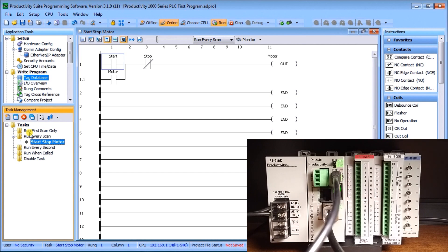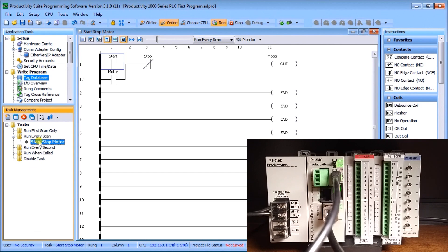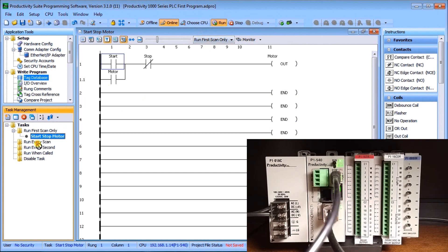Under Task Management there are several run options: Run First Scan Only — ideal for resetting values during initial PLC boot-up; Run Every Second — good for math operations that don't need to run every scan; Run When Called; and Disabled Task, where you place programs under development before moving them into the active program. To change the task type, you can click, hold, and drag it — for example dragging 'Start Stop Motor' up to Run First Scan Only, then back down to Run Every Scan.